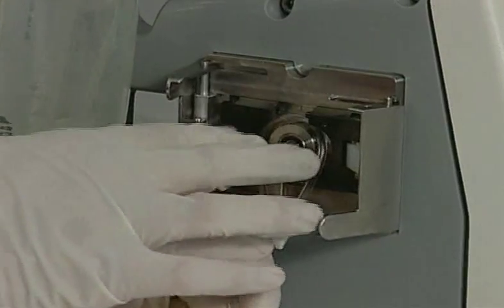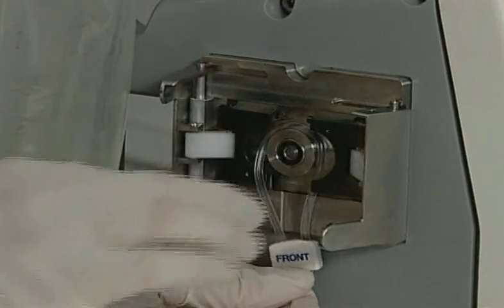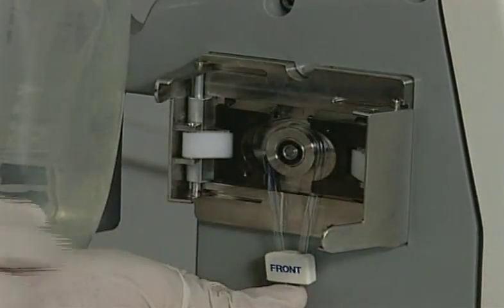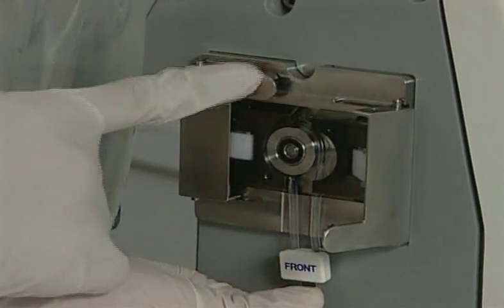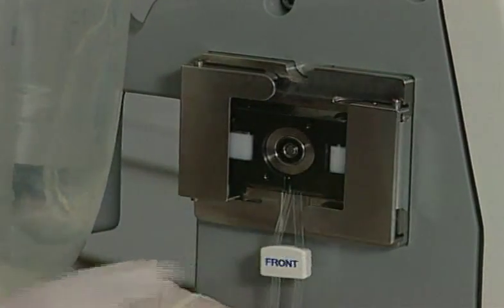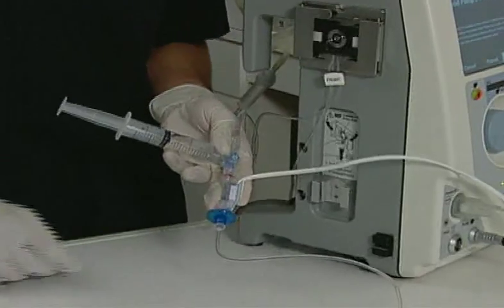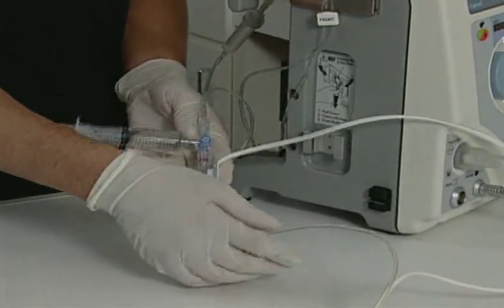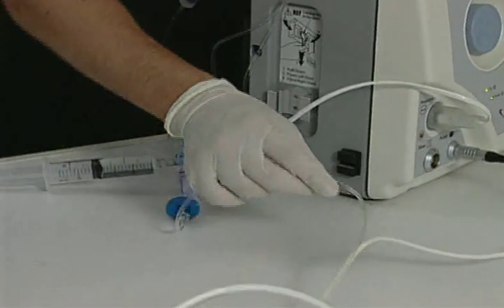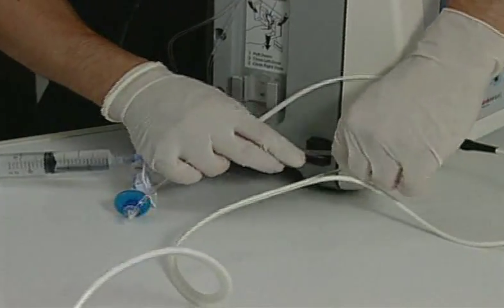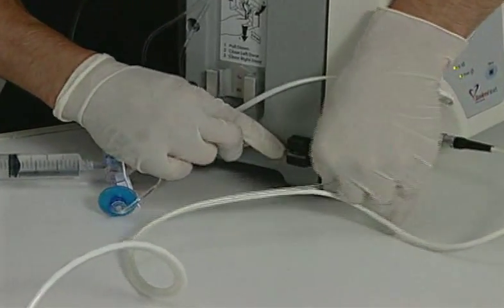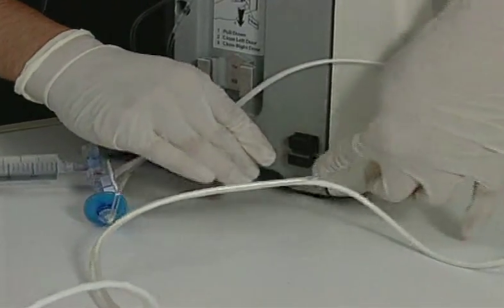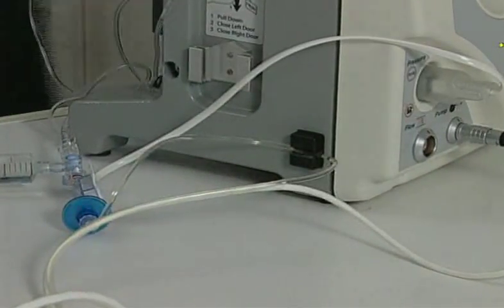Open the two doors on the infusion pump and place the loop around the cam in the infusion pump. Pull down on the tubing loop. Close left side infusion door first, then right side. Insert a portion of the pump infusion line between the bacteriologic filter and the protective sheath on the pump communication line into the air bubble detector by simultaneously pushing and pulling the pump infusion line.